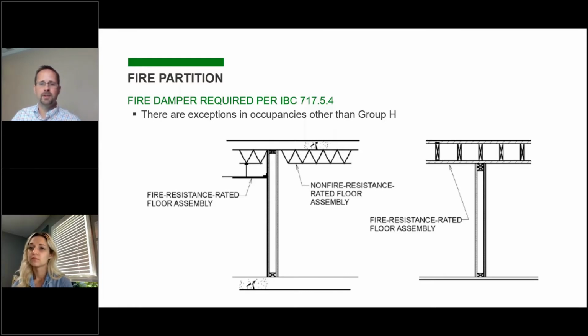So in some older buildings, there can be a little bit of confusion where you have dampers in one area, but not another. But it's important to understand the codes that are in play when a project's being designed and not just match what was there before, assuming that that was correct. Obviously, there's other leeway for tenant walls where they aren't required to be fire rated for any other reason. They don't require dampers in those situations. And then some small ductwork. Again, like we said, for the provisions regarding the fully ducted system, the same considerations need to be made in code calls to identify how the AHJ is going to interpret those exceptions, to make sure that they don't have some stricter interpretation than what would be common.